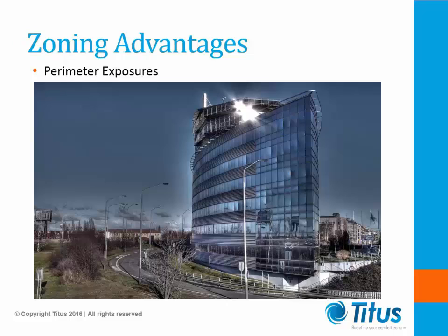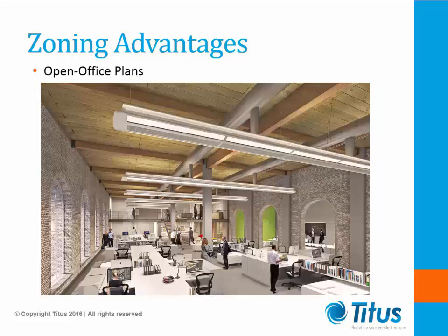When it comes to zoning, chill beams offer some pretty big advantages over all air systems. The inherent benefits of a chill beam system, which minimize system airflow, allow for more diffusers to be installed or included in a zone. With all air systems, the ductwork very quickly becomes too large and boxes become too loud to have a single perimeter exposure tied into a single thermostat or control valve. This also lends itself to large open office plans where you can have a single thermostat controlling the water valve for all of the beams in this single large space.